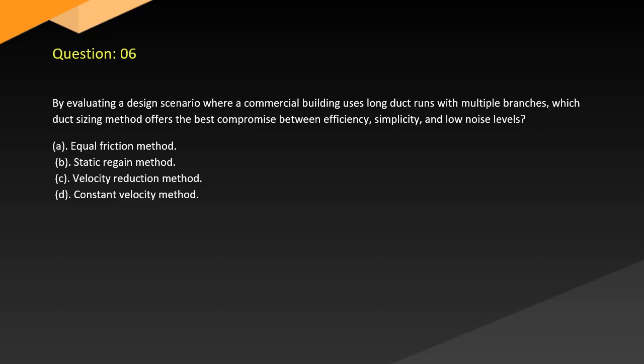Question 6. By evaluating a design scenario where a commercial building uses long duct runs with multiple branches, which duct sizing method offers the best compromise between efficiency, simplicity, and low noise levels? A. Equal friction method. B. Static regain method. C. Velocity reduction method. D. Constant velocity method.